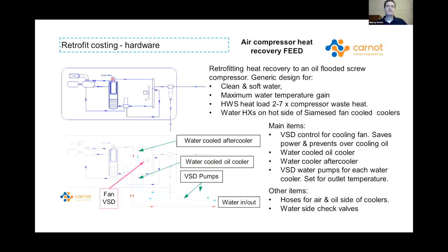So this is a suggested system. There are lots of different ways to do things, and it depends upon what you are planning to do. The intent of this system is to give you the hottest water possible. So small water flows, and it's a generic design for clean and soft water. You'd use this if the hot water system load was say 2 to 7 times that of the compressor waste heat. And it also considers the heat exchangers as Siamese on the hot water side.